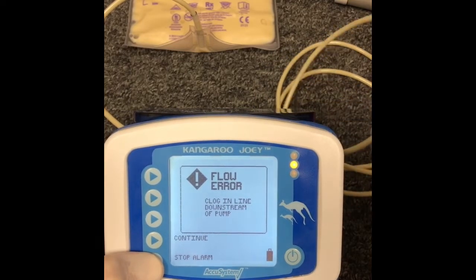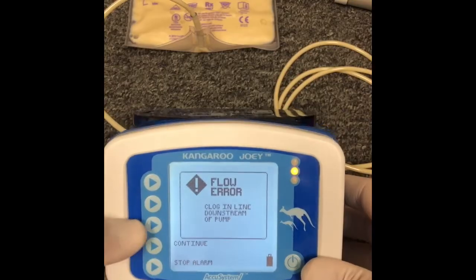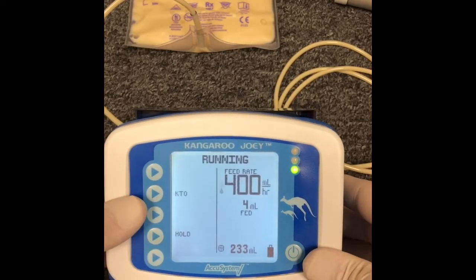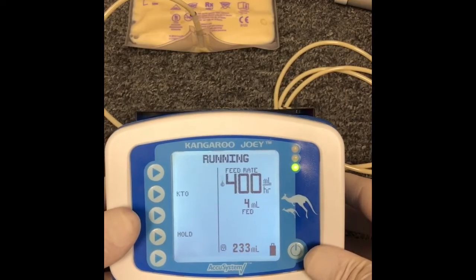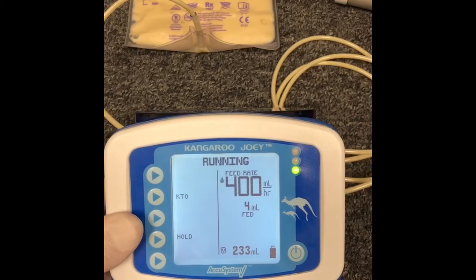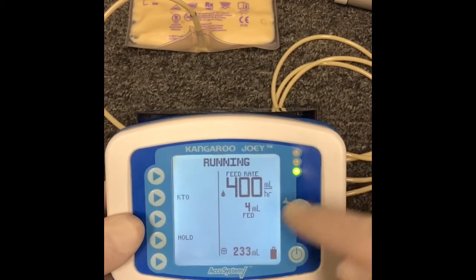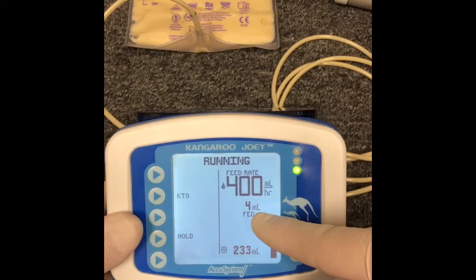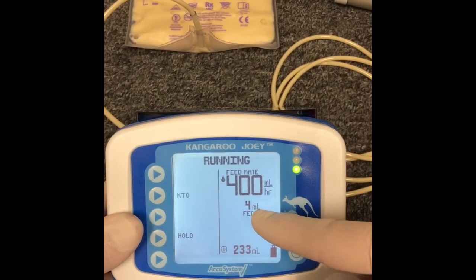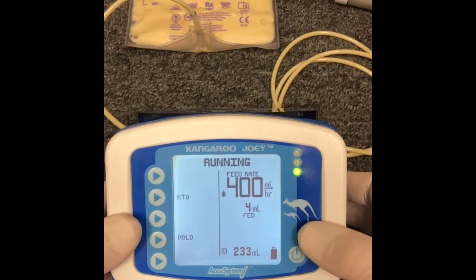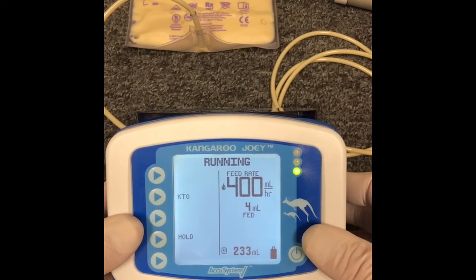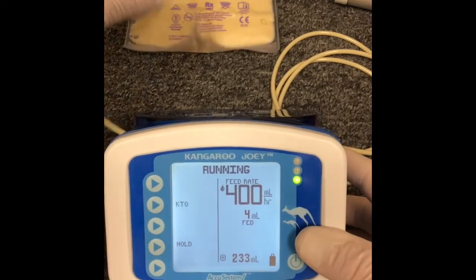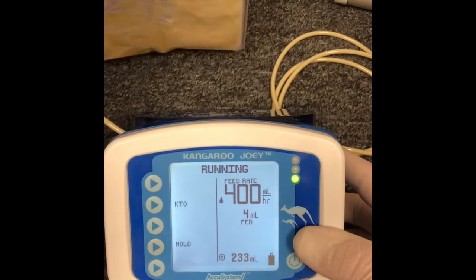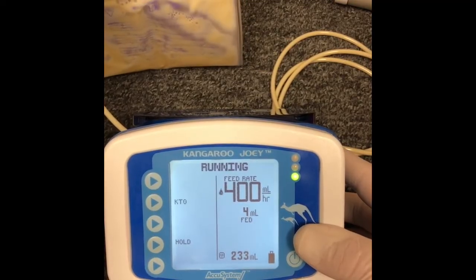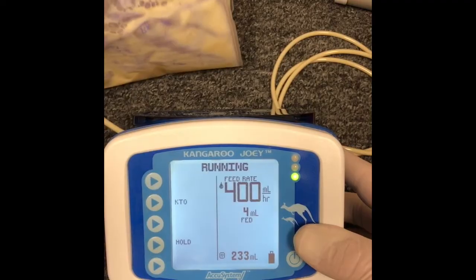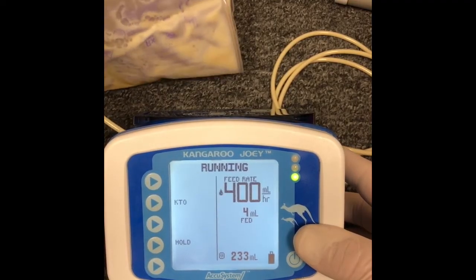So I'm gonna go ahead and remove that issue. Once the issue is removed, you can go ahead and try to do continue, and it will continue on at that point and say, all right, if there's no more flow, I'll keep running. Right now I'm looking at the end of my tubing and I'm seeing it flowing, so I know it's running again. You can see here, it should have really gone up for 1 more milliliter fed for how long it was running there. So it even knew that there was nothing running. It just took a moment for it to get that alarm sequence to happen. The other alarm that it will have is that once the bag is empty, if I was to simulate it pulling up air through here, it will start to alarm basically no food, which is basically saying that there's no food left in the line, of course.